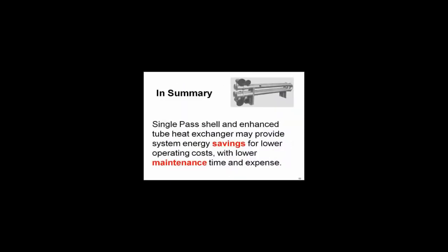So another comment on a single pass heat exchanger, and you may want to take a look at this based on what we're seeing. They do handle fouling better. You can only get about a four degree approach versus the plate at two, but the plates foul a lot quicker. And once you foul a plate, you're going to lose efficiency. You may find that single pass counterflow heat exchangers save you more money and reduce your maintenance costs. It's certainly a good option to take a look at.